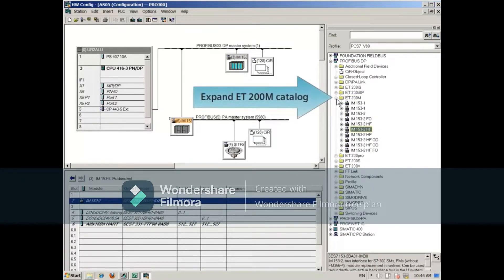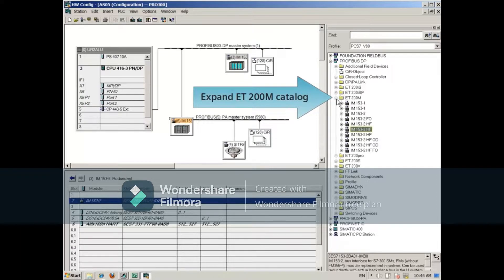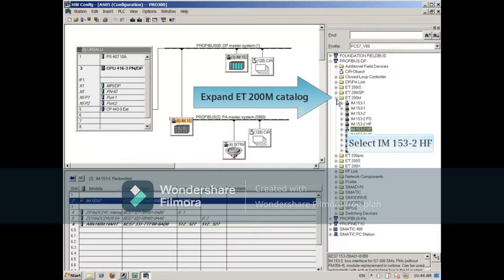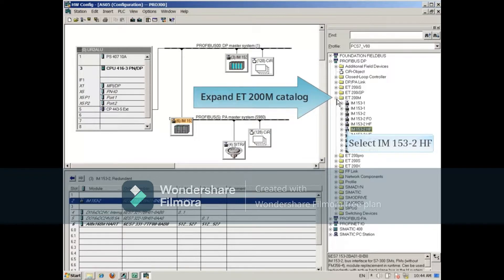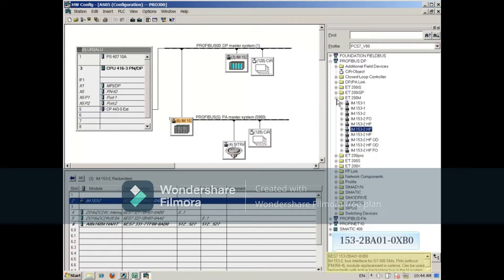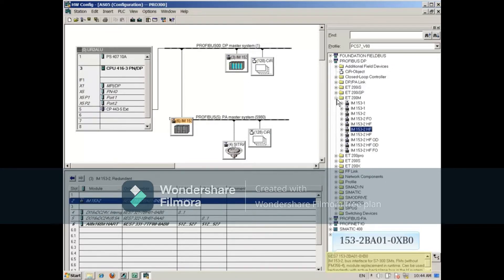Expand the Profibus DP slash ET200M catalog and select the IM153 choices until the order number at the bottom matches the one in Hardware Config. In this example, it's 153-2BA01-0XB0.